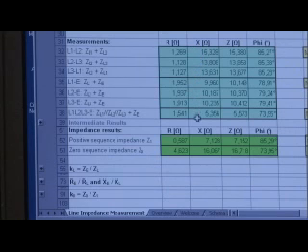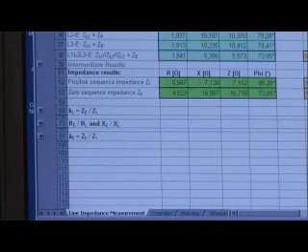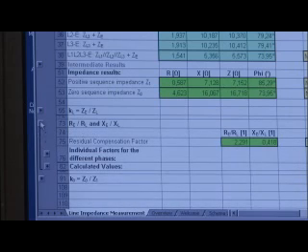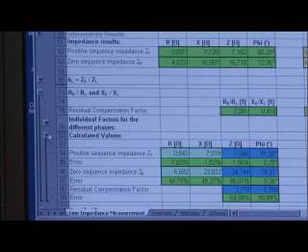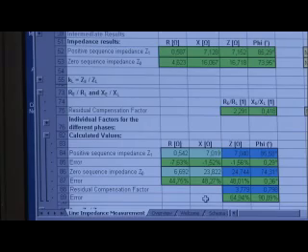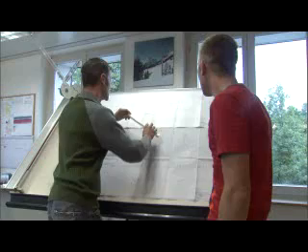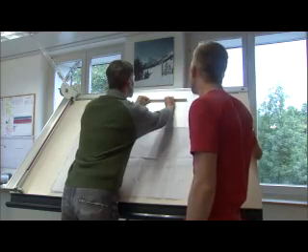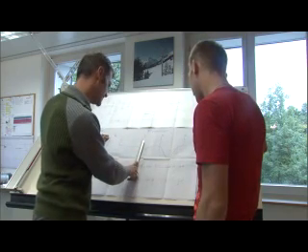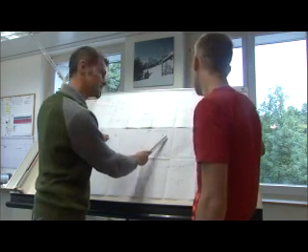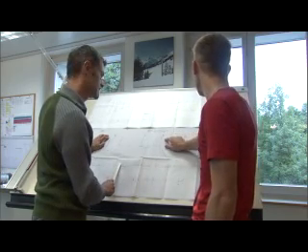As an example, a large utility requested our device for measuring the parameters to calculate the K factor of a line where zone overreaches had occurred. The measurements showed that whereas the positive sequence impedance matched within a few percent, the imaginary part of the zero sequence impedance was measured with an error of 48 percent — 16.1 instead of 23.8 ohms. Weeks later, the reason was found: the company's database contained an incorrect DC resistance value for the ground wire used. Measurements to verify the calculation of relay settings can prevent overreaches and are obviously a good idea.